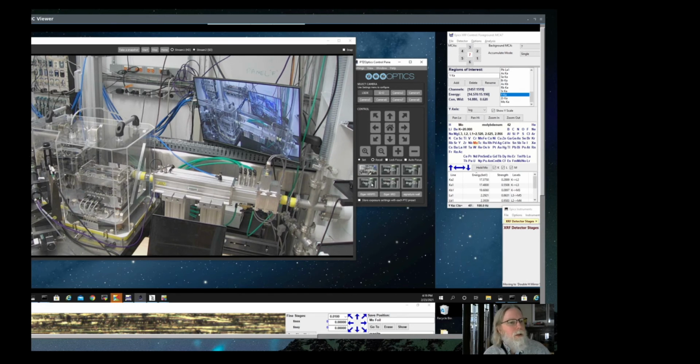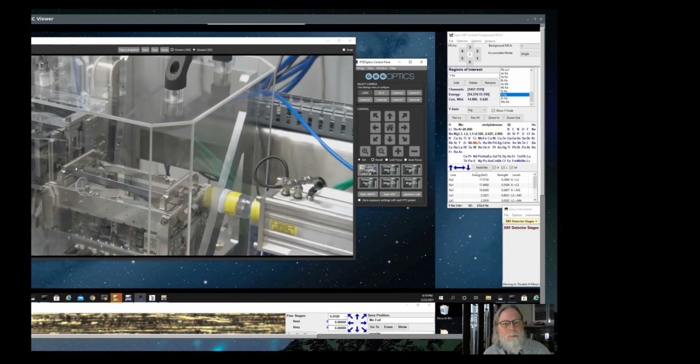If I zoom in on the mirrors there, you can see that those are a flat piece of silicon, about 200 millimeters or a little bit longer, and that's pitched at somewhere between 3 and 5 milliradians, depending on the day and the kinds of x-rays we want to get onto your sample. You can see there's a metal coating that's rhodium on top of the bare silicon. Although it's a flat piece of silicon, we bend it into an ellipse by pushing down on these bars on the top.